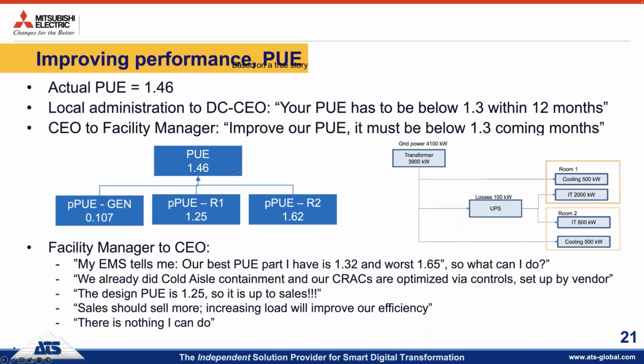If you look at the green grid, they also have a PUE decomposition. The partial PUE of room 1 is 1.25, the partial PUE of room 2 is 1.62, and the general infrastructure part is 0.107. So the facility manager tells the CEO, my EMS tells me our best part of the PUE is 1.3 and the worst part is 1.6. So what can I do? We already did cold or hot aisle containment and our CRACs are optimized via our control vendor. I know the design PUE is 1.25, but that's at a completely filled data center.